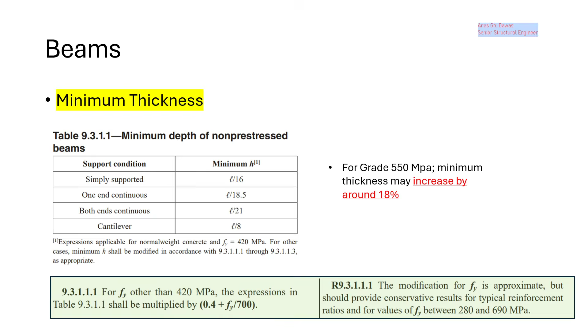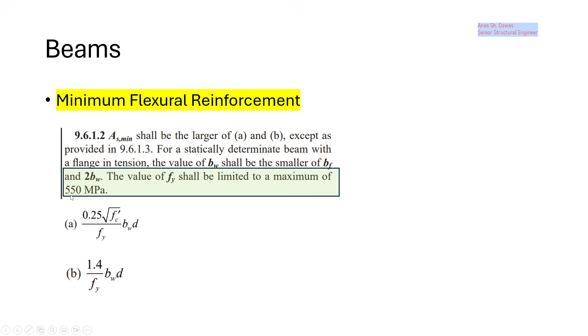Here also, for minimum flexural reinforcement, the maximum value that can be used to compute the minimum flexural reinforcement of the beams is 550 megapascal. So let's assume that you would like to use 690 megapascal. When you calculate the minimum flexural reinforcement, you have to use a maximum value of 550 megapascal. So if your beams, let's say, are governed by the minimum value, you cannot take the full benefit from 690 megapascal. The maximum value that can be used at that time is 550 megapascal.